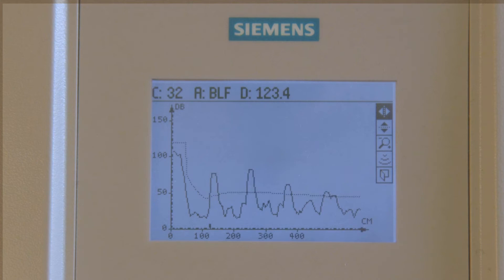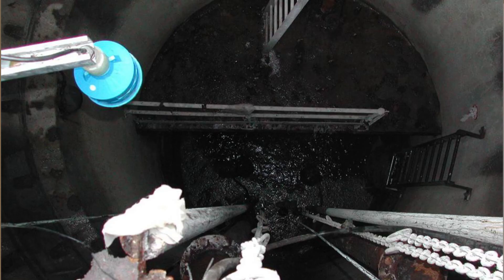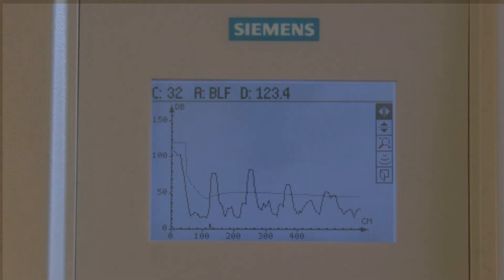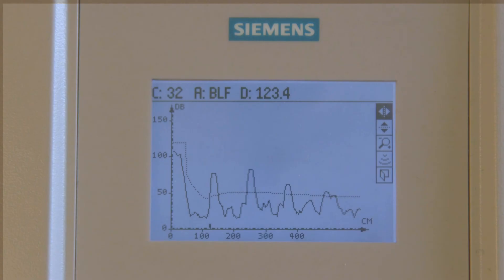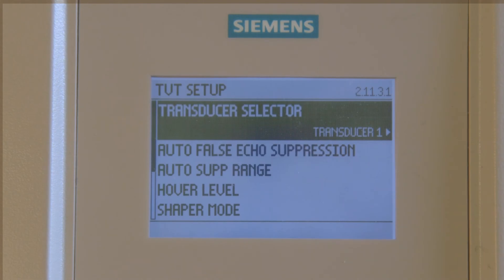Ideally, the auto-false echo suppression is performed on an empty vessel. In this example, that's not possible, but it can be performed in the area currently exposed. We need to determine where to set the auto-false echo suppression range. It should always be 50 cm less than the actual material echo, above the bottom of the vessel, or the top of the material if the vessel cannot be emptied. Using this guideline, we know to set the false echo suppression range at 200 cm.